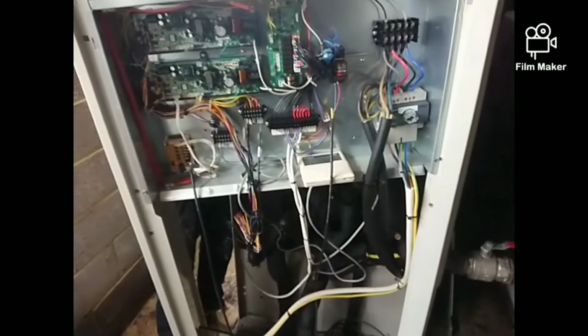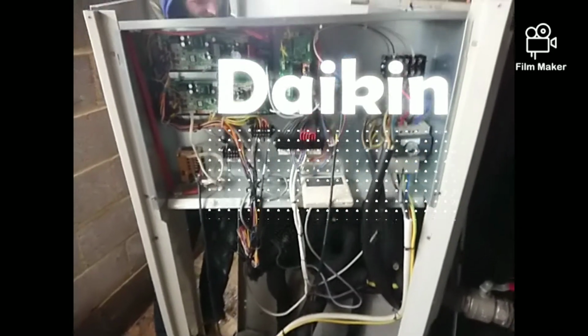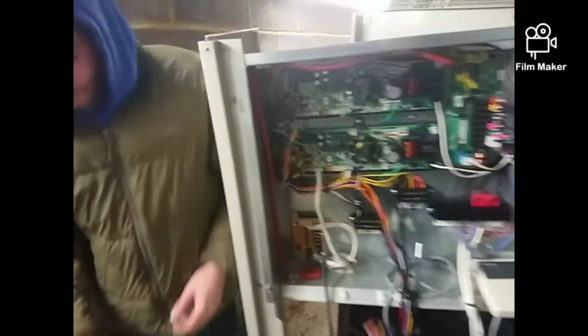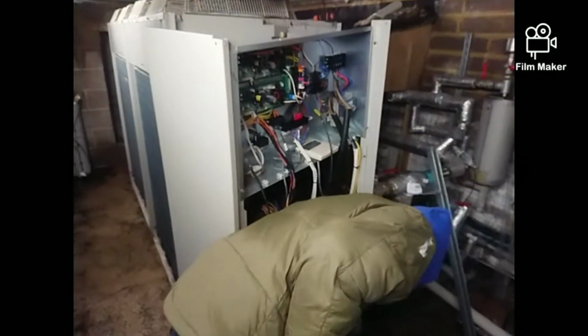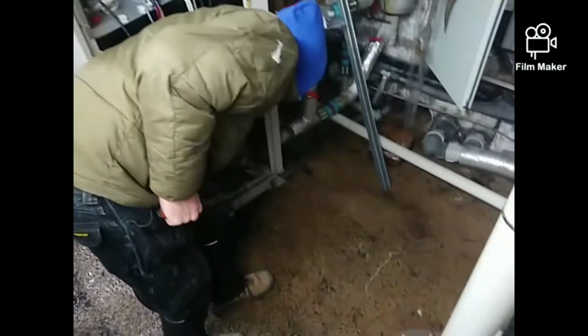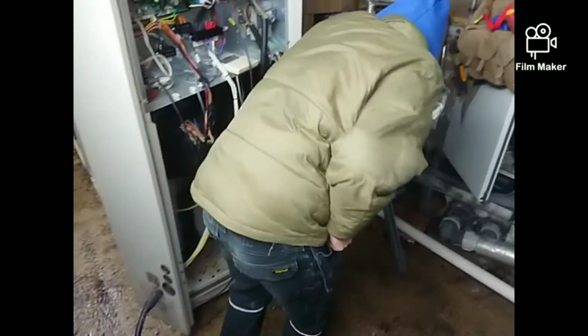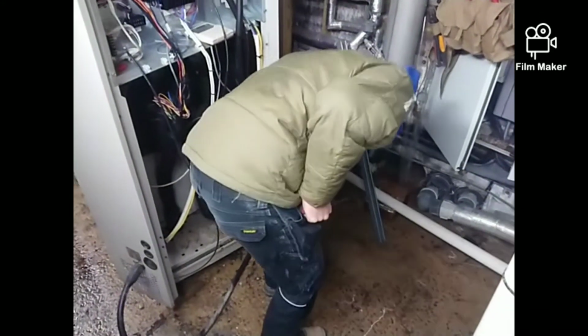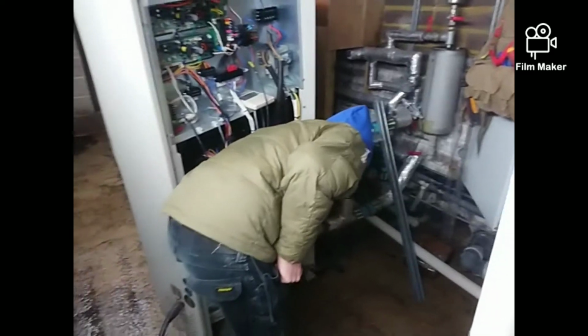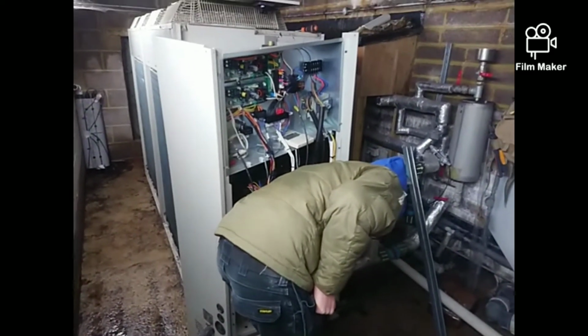The initial problem was A6 fault, which is quite common on these. I've only come across it once before, but the systems are both exactly the same. Yeah, we will drain the water out. The systems are both exactly the same as in what they do. And you need to turn the water off, Ash, at the isolation points. Just hold fire there, Ash, while I'm just doing this.